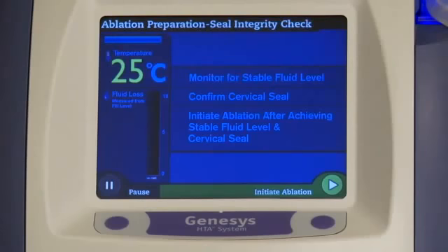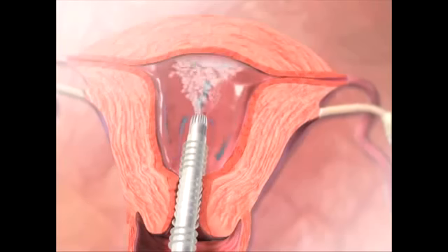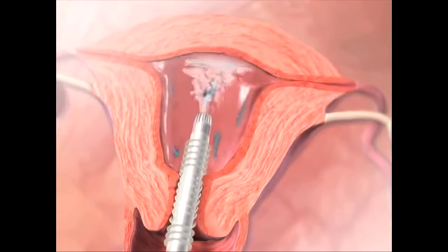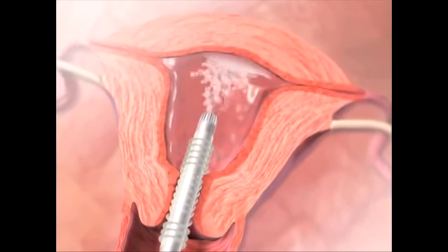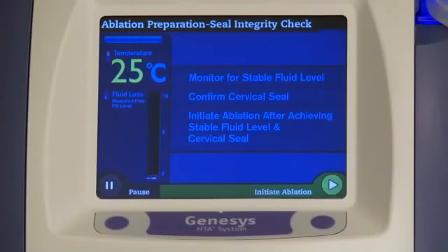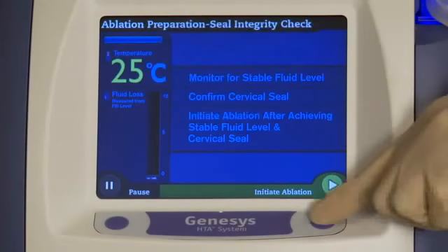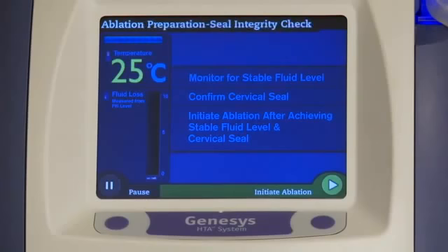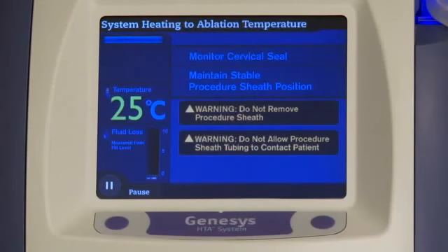Before ablation is initiated, the system performs a seal integrity check. During this phase, room temperature saline is circulated in the uterus. Throughout this closed-loop phase, fluid level and temperature are monitored and displayed on the screen. Once you observe a stable fluid level and are confident that you have a good cervical seal, initiate ablation by pressing the right console button. The Genesys console will now begin heat-up of the saline.